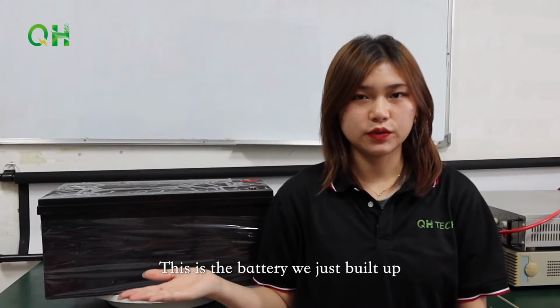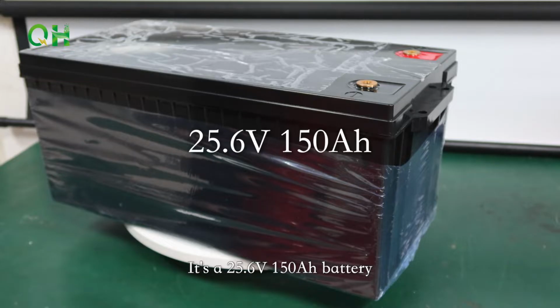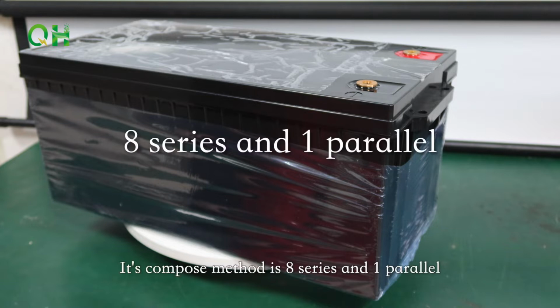This is the battery we just built up. It's a 25.6 voltage, 150 ampere-hour battery, composed of 8 series and 1 parallel. Parameters: dimension 522 x 240 x 218 mm, weight 28 kg. Charging current 150 amp, discharging current 150 amp. Working temperature -20 Celsius to 60 Celsius.